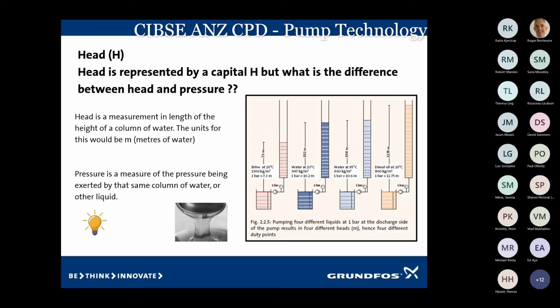One other thing to consider when we're talking about the pump head is if we're pumping products that aren't water at 20 degrees. All pump performance curves are designed for water at 20 degrees. If we change the fluid, if we're pumping glycols, then the density will change, and that will then impact on the performance of the pump. The pump will still produce flow and it'll still produce pressure, but it might not necessarily give you what you think you're going to get. So in other words, if you look at the second guy in here, we've got a little pump sitting there above the water, and it's 20 degree water, and the density is about 1000.